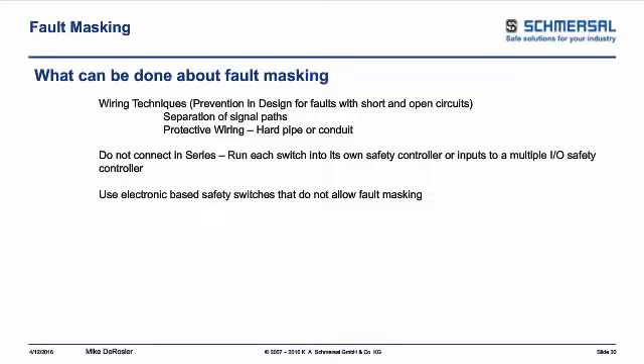So you want to ensure that the task that you're performing either falls under lockout tagout, or if it does fall under machine guarding where you need to gain access while the machine is running to do an index or a jog, what safety circuits are in there, can you justify it? Make sure you do a task-based assessment to know that this can be a safety interlock condition. Otherwise, it is lockout tagout, and thumb screws still wouldn't be good unless an interlock switch is on there. And if anything you do falls under lockout tagout, why even have the interlock switch? You're better off making sure you have the proper hardware that people can access.